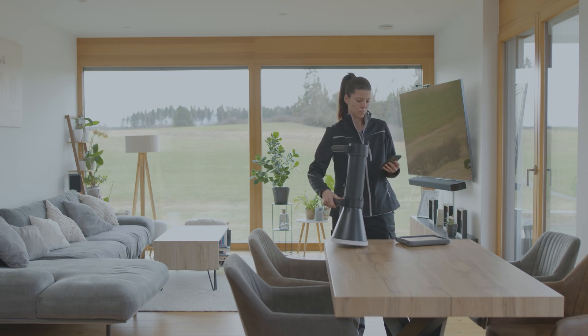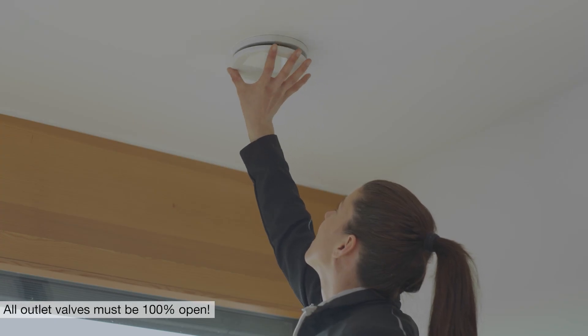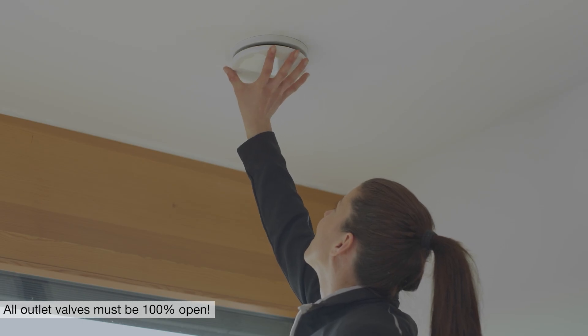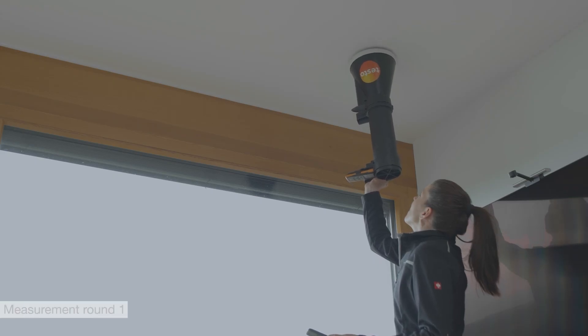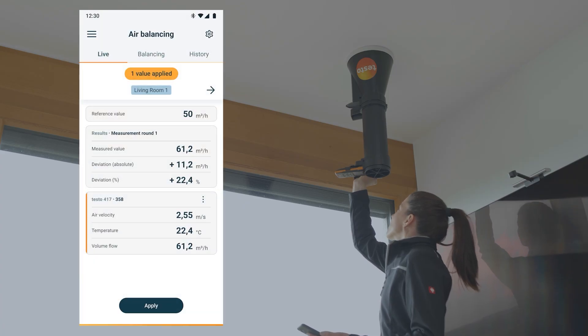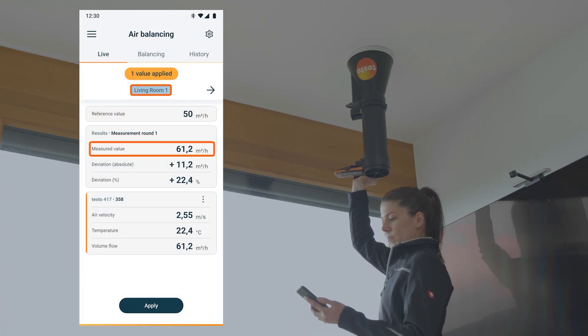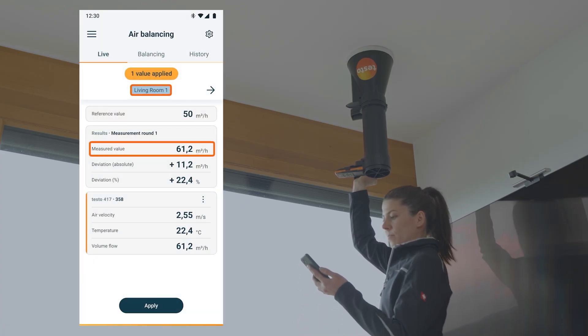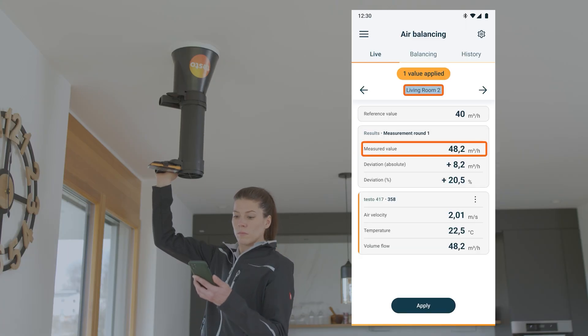For this purpose, the volume flows of all outlets are recorded. It is important that all outlet valves are 100% open. For each measurement, the measuring instrument is held with the funnel over the outlet so that all the air is directed over the vane. The measurement value can then be recorded with the Testo 417 and the Testo Smart app.